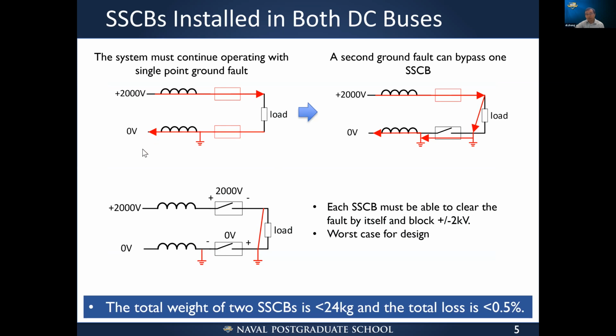So the system must continue operating with a single point ground fault, just like this, right? If you have a single point ground fault, one pole is at 0 volts and the other pole will become like 2,000 volts, right? So if we have solid state circuit breakers in both DC buses, and the system is running with a single point ground fault already, and a second ground fault happens, the 2 ground faults can bypass one solid state circuit breaker. So if we have both breakers, then the breaker that is not bypassed can be turned off to clear the fault, right? Just like this.